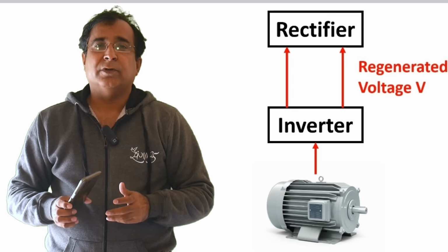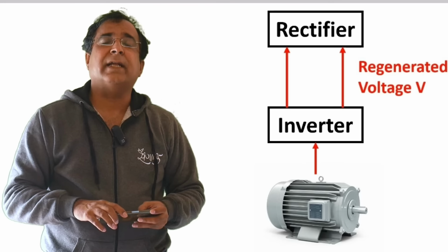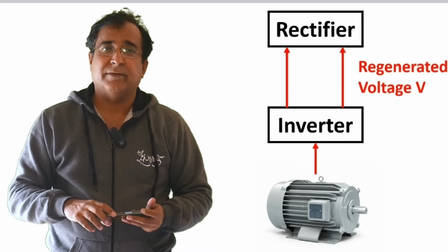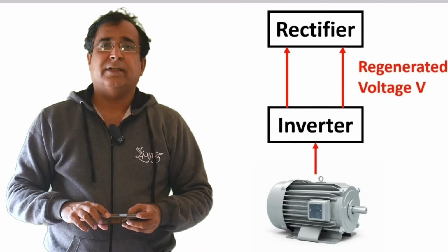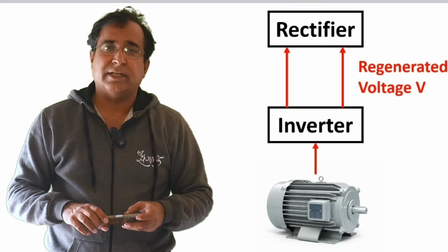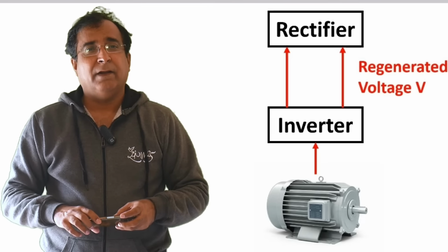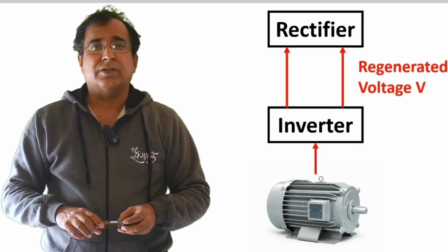In regenerative mode, the electrical energy flows in reverse, with the motor supplying electrical energy back to the DC bus. This reverse energy, when increased to a certain level, raises the voltage level on the DC bus. See the equivalent circuit shown on the screen. Now we have two power sources on the DC bus. When the motor load source voltage rises to the set limit, the VFD gets tripped. These two sources act as batteries with different voltages.